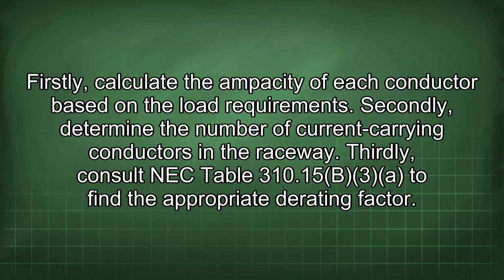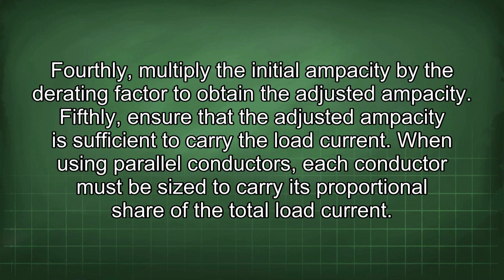Firstly, calculate the ampacity of each conductor based on the load requirements. Secondly, determine the number of current-carrying conductors in the raceway. Thirdly, consult NEC Table 310.15(B)(3) to find the appropriate derating factor. Fourthly, multiply the initial ampacity by the derating factor to obtain the adjusted ampacity. Fifthly, ensure that the adjusted ampacity is sufficient to carry the load current.